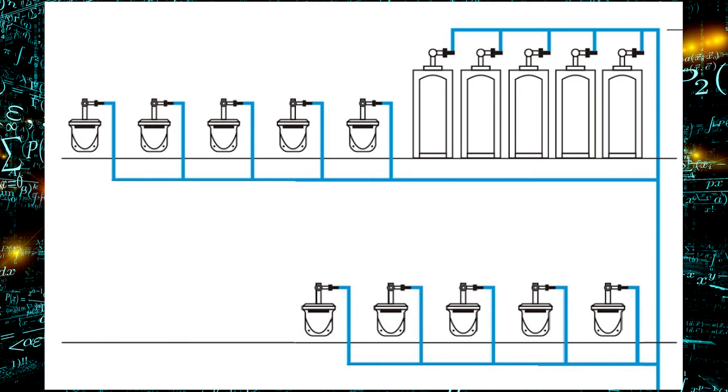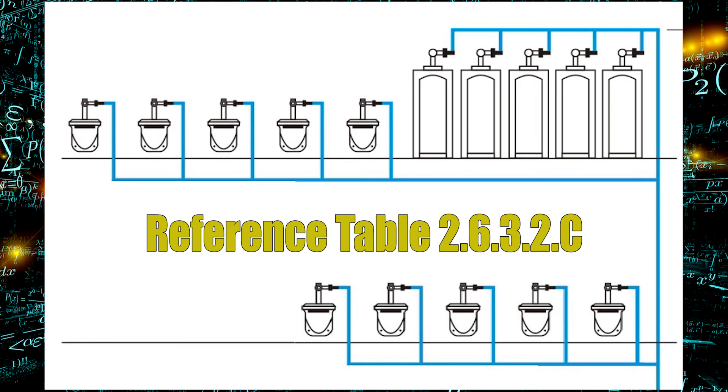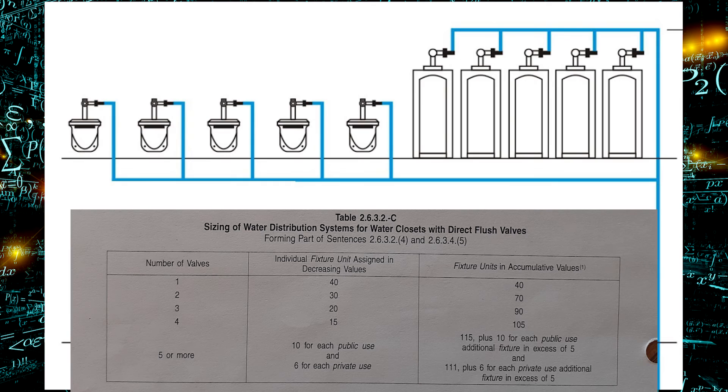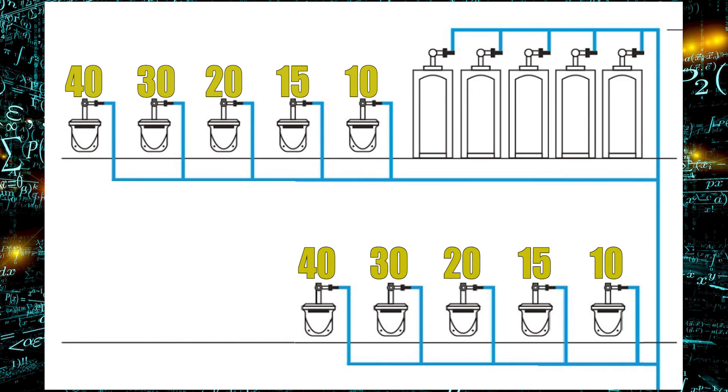So now we have a direct flush valve set up here. What you see on the top floor is five direct flush valve water closets, right beside five direct flush valve urinals, and the lower floor down is five more direct flush valve water closets. Now we're going to label out the fixture units like we're told to in table 2.6.3.2.C for the water closets. On the far left-hand side here, we have 40 fixture units going to this water closet. The next one down is 30, the next one down is 20, the next one down is 15, and the next one down is 10. Now the five water closets along the bottom floor are going to look exactly the same as the five upstairs.